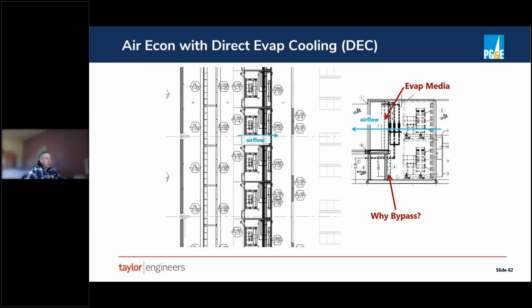The other reason to have a bypass is for energy efficiency, right? If you're in the data center with an air economizer, most of the time you're going to be at 100% economizer cooling or mixing, and you won't need any direct evap. And so in those periods, if you had a bypass here, you save the pressure drop in this media, but that's not the main reason. The main reason is the temperature control. This data center had a fatal flaw in that the bypass was right under the evap media right before it went into the data center.